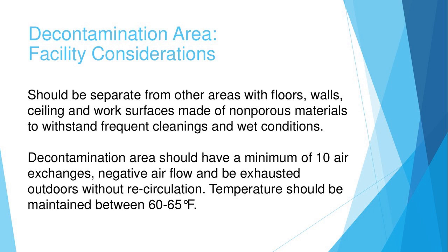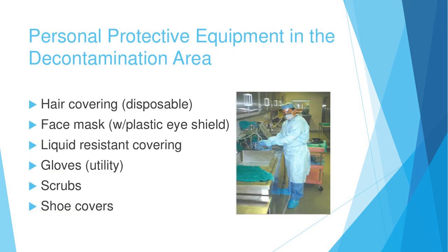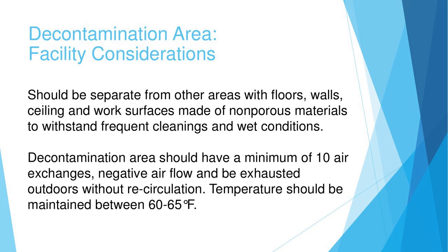But to do this, we need to make sure that our decontamination area is set up appropriately. Our decontamination area that the facility must consider should be separate from other areas with floors, walls, ceiling, and work surfaces made of non-porous materials to withstand frequent cleaning and wet conditions. Decontamination area should have a minimum of 10 air exchanges, negative airflow, and be exhausted outdoors without recirculation. Temperatures should be maintained between 60 and 65 degrees Fahrenheit.